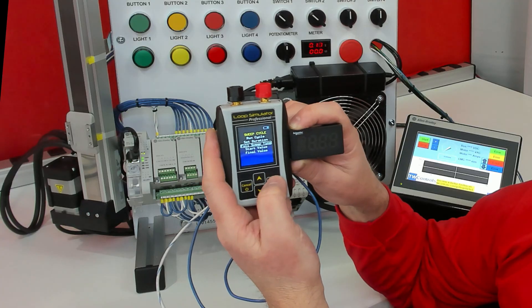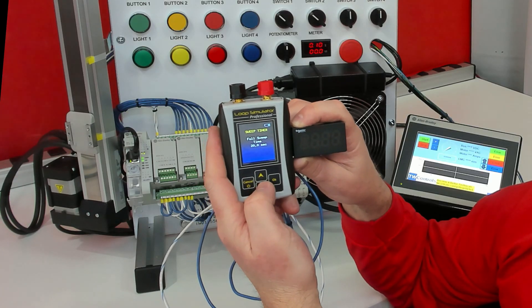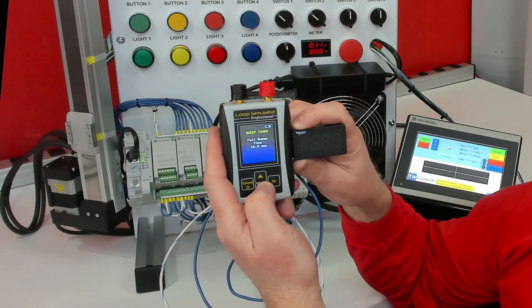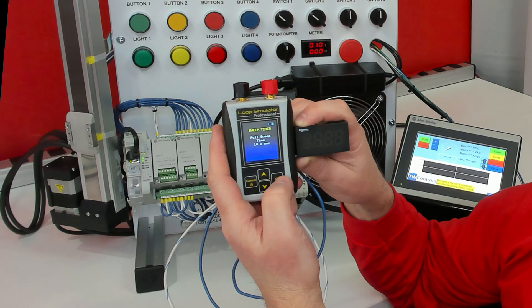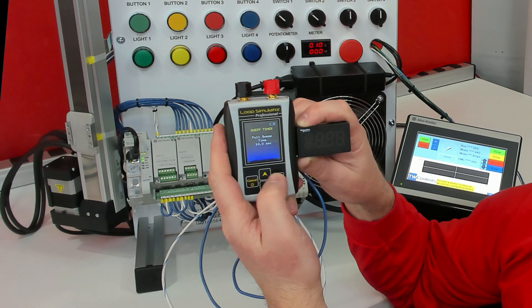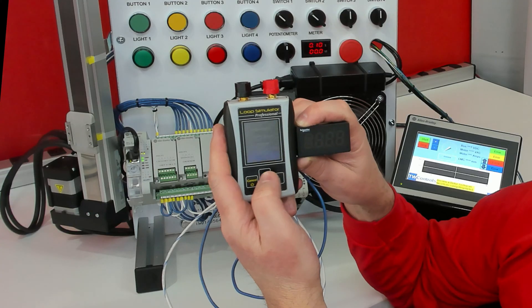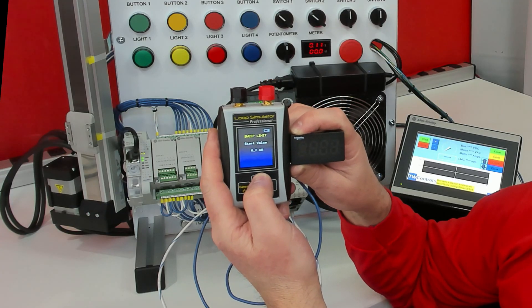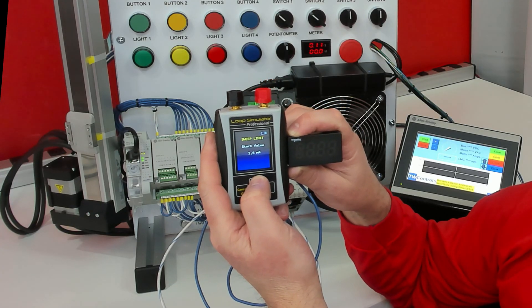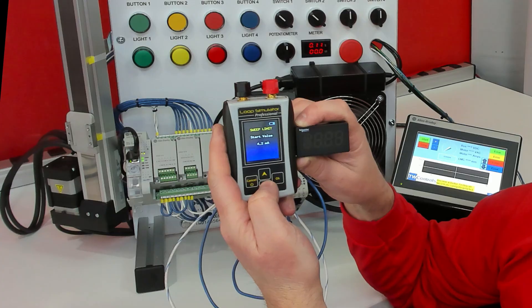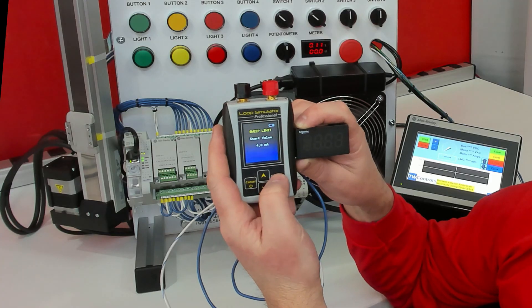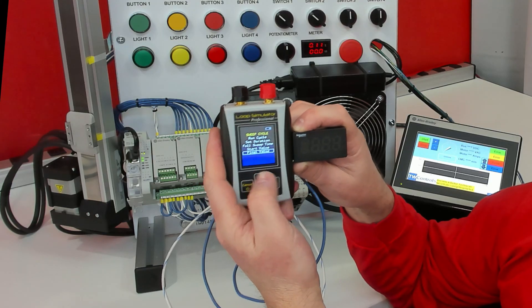Then we'll go down to the Full Sweep Time. It's currently set to 20 seconds, so I'm just going to bring that down to 10. For Start Value, I'm going to set it to 4 mA. And our Final Value, I'm going to leave at 20.